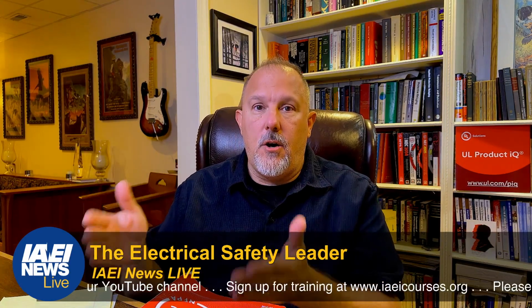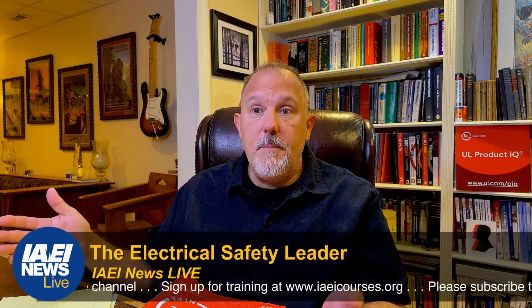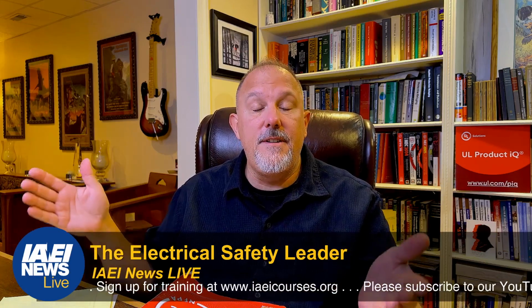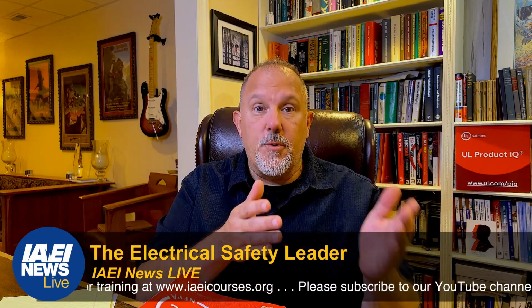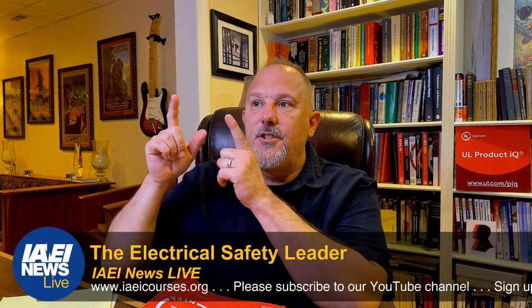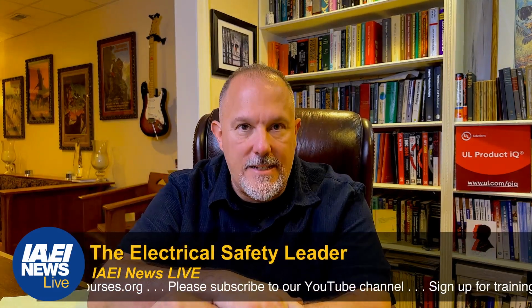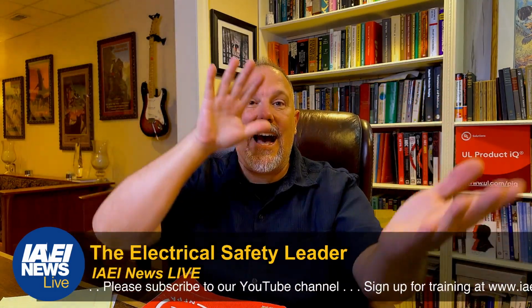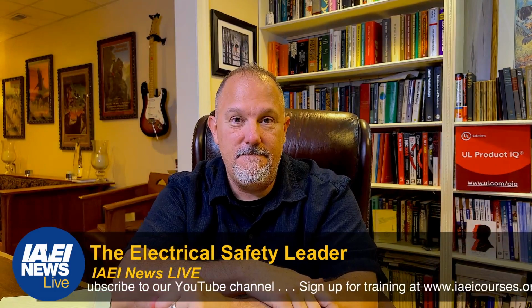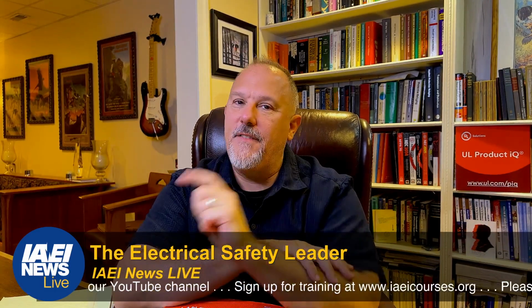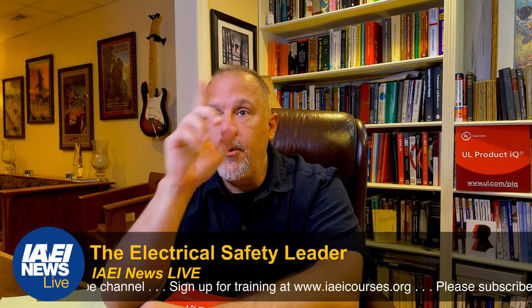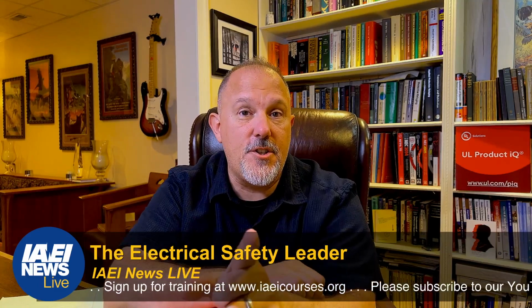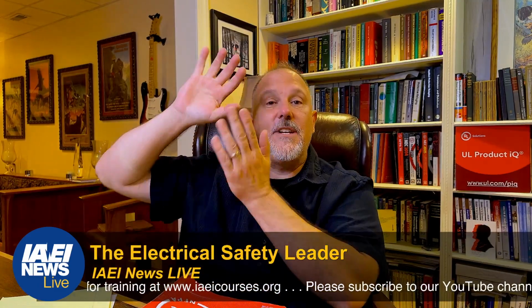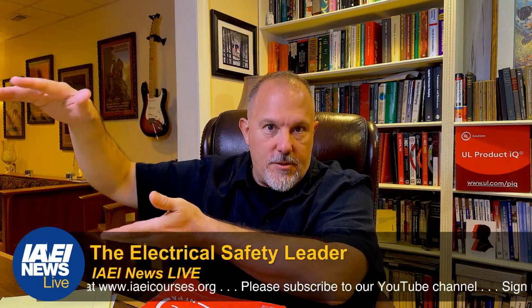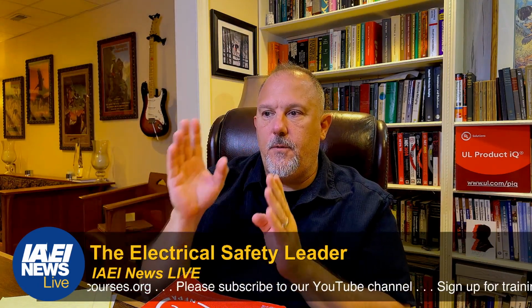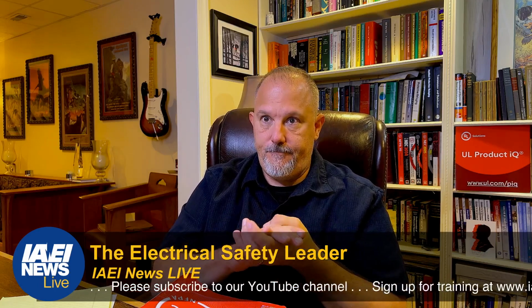So now you might understand why Article 242 is not called surge protective devices, because it's not just about surge protective devices. It covers surge protective devices and surge arresters. And no, they are not identical. All right? They're not identical. So, informational note number 1, very valuable. It's an IEEE document. It's not a UL standard. UL 1449 covers surge protective devices, and there was a term in there, secondary surge arrestor, because surge arresters are on the utility side, not the utility side, on the medium voltage side.